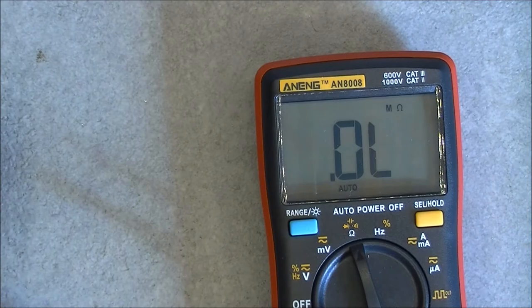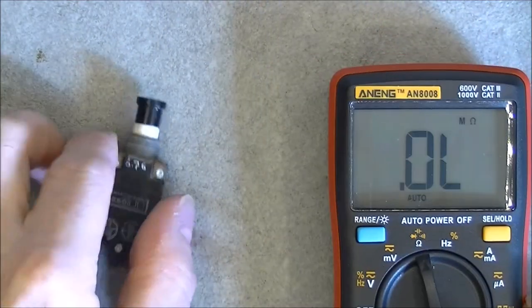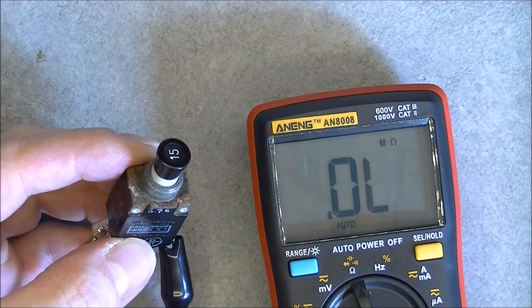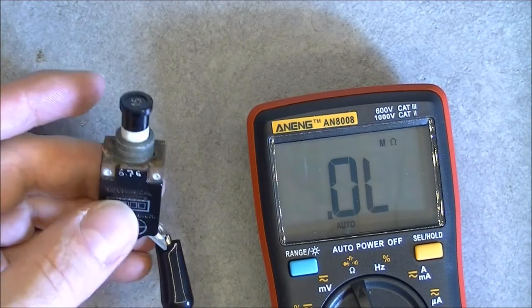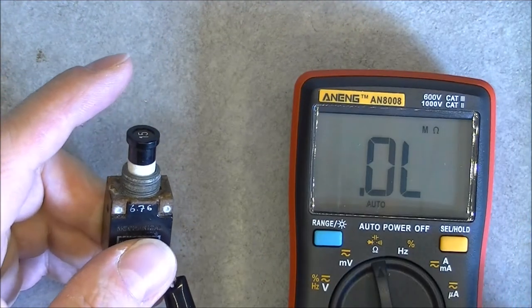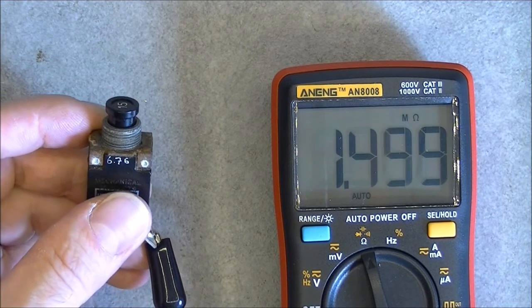What happens here? The circuit breaker is in the open position, so it is normal that it has infinite resistance. But if I trigger it, look at what we have. We have a very high resistance of over one megaohm.